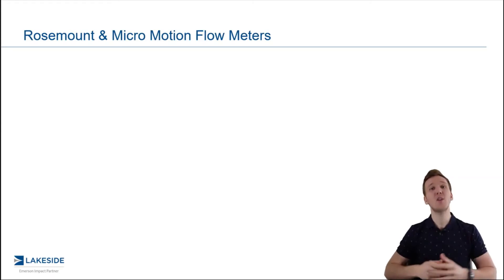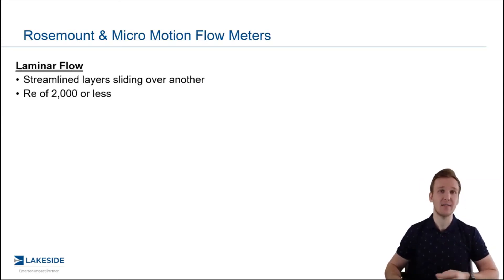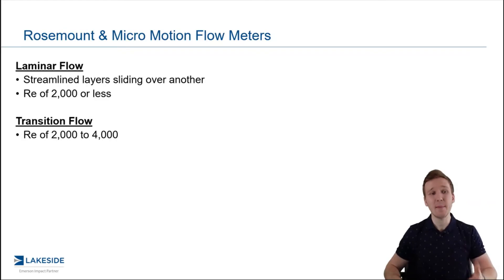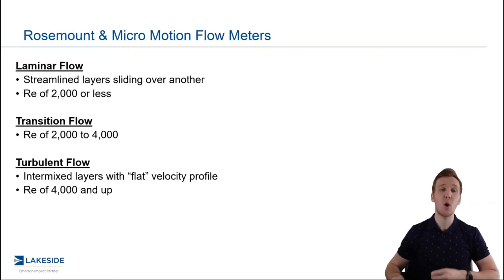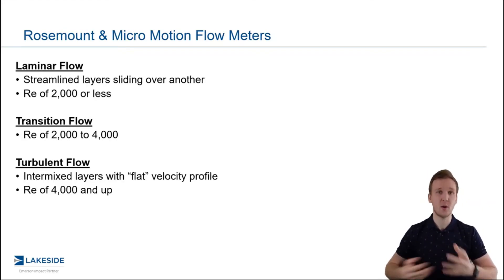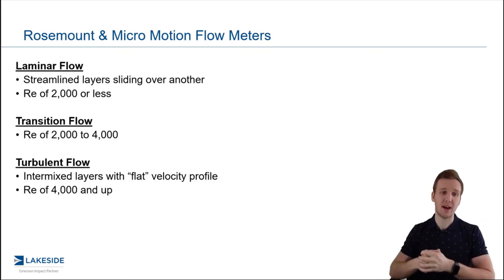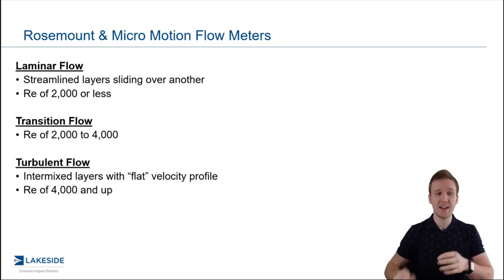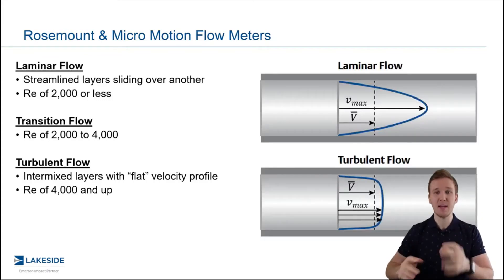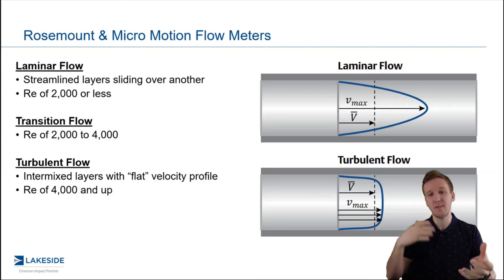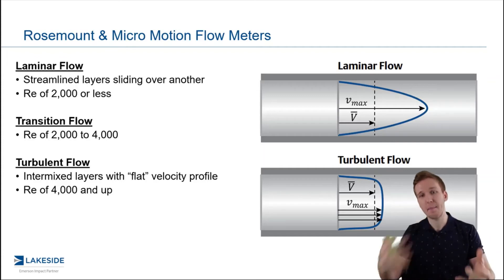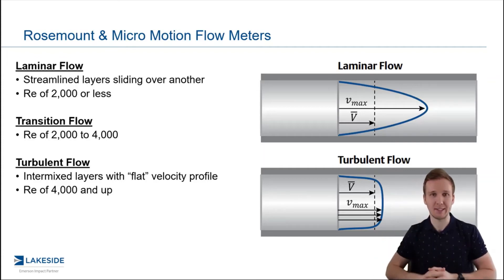Now, depending on the Reynolds number that you have in your system, it will impact how it's classified. Is it laminar flow, is it transition flow, or is it turbulent flow? This is going to depend on whether your Reynolds number is 2,000 or less, 2,000 to 4,000, or above 4,000. And the difference, as you can see depicted here, really has to do with the average velocities versus the maximum velocity in the piping system.